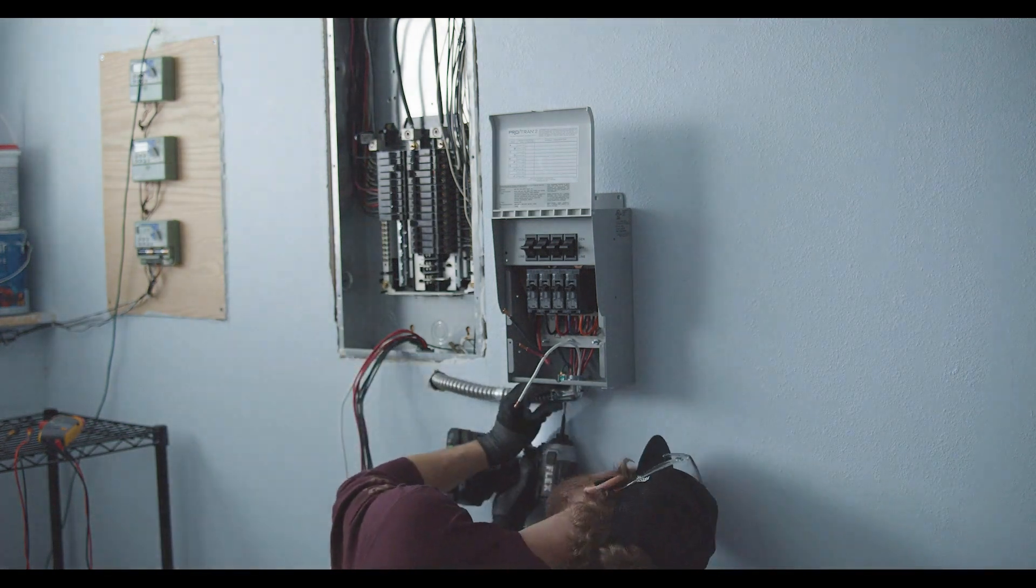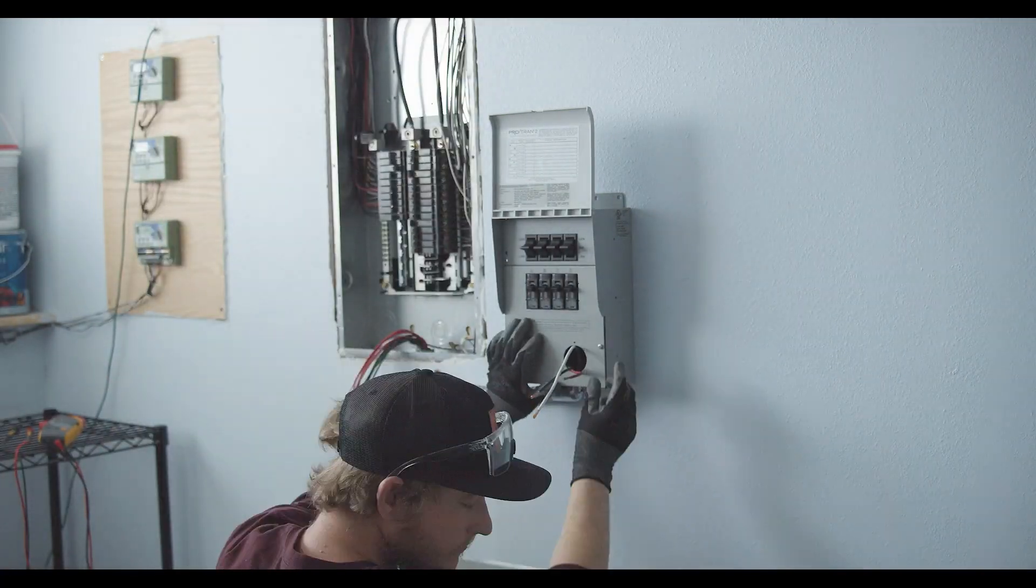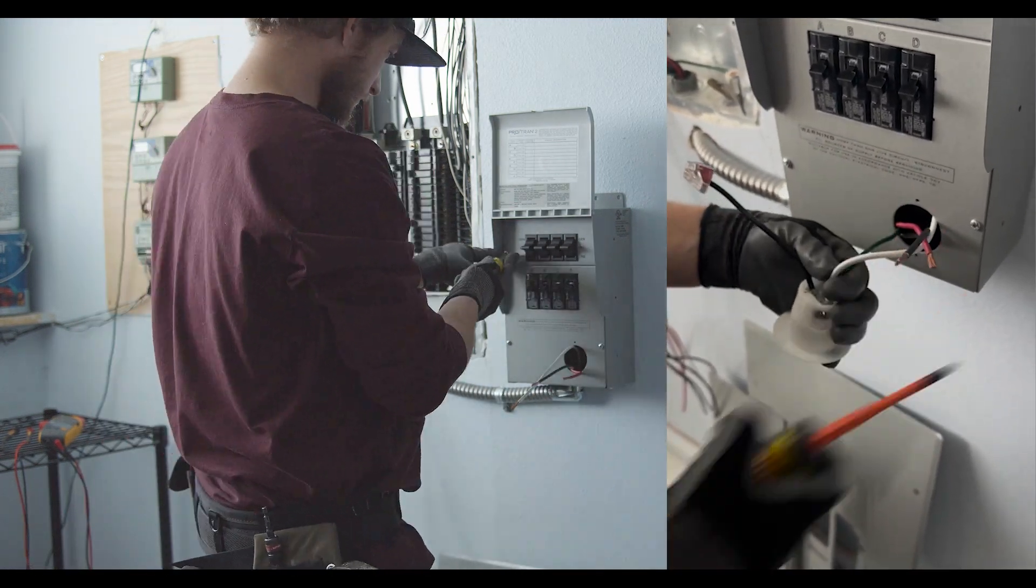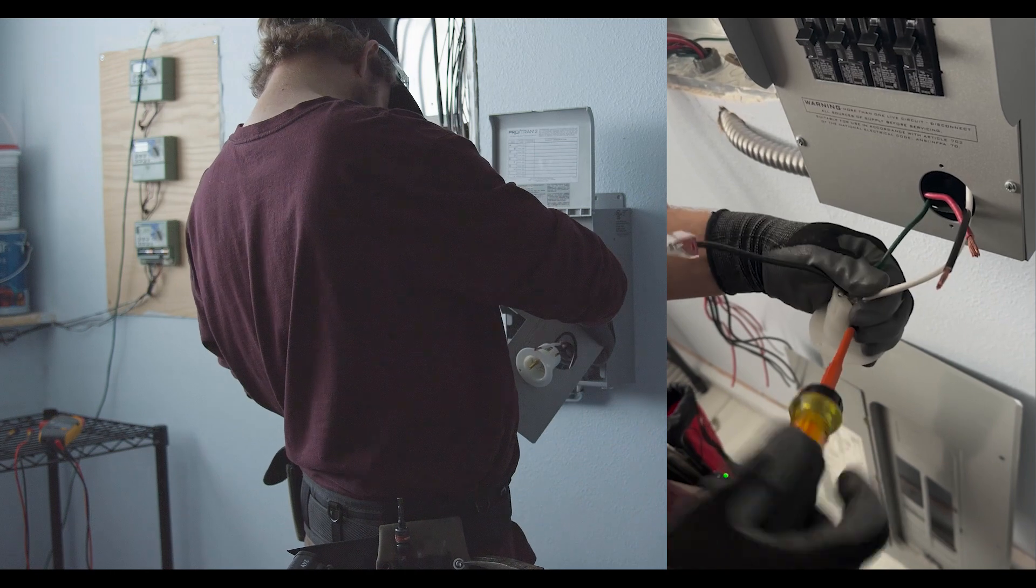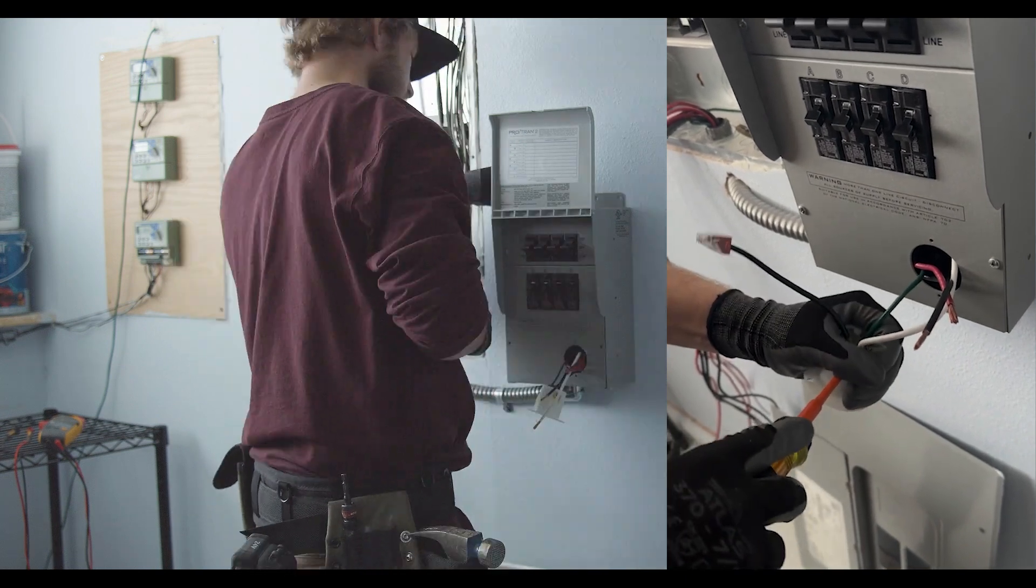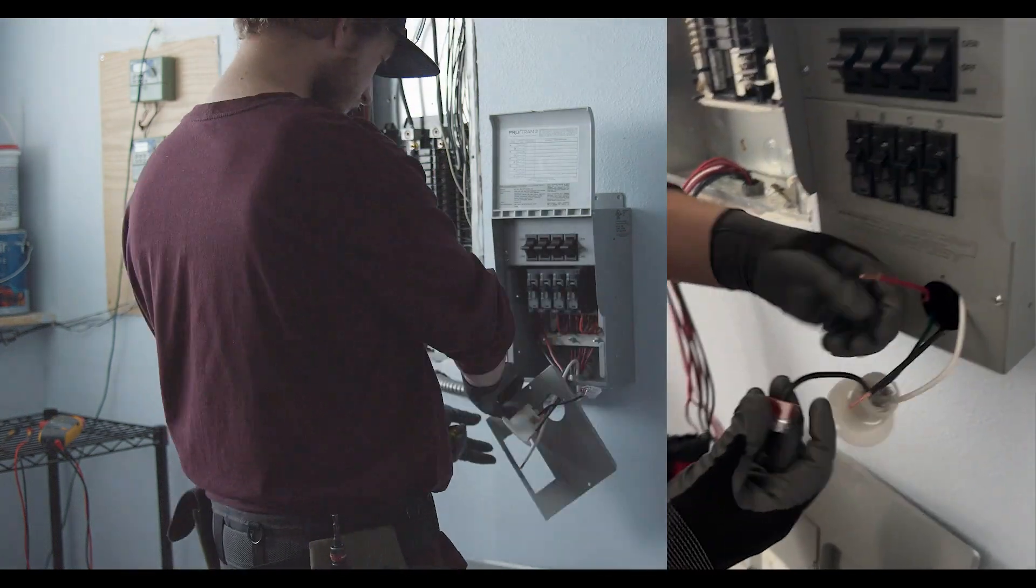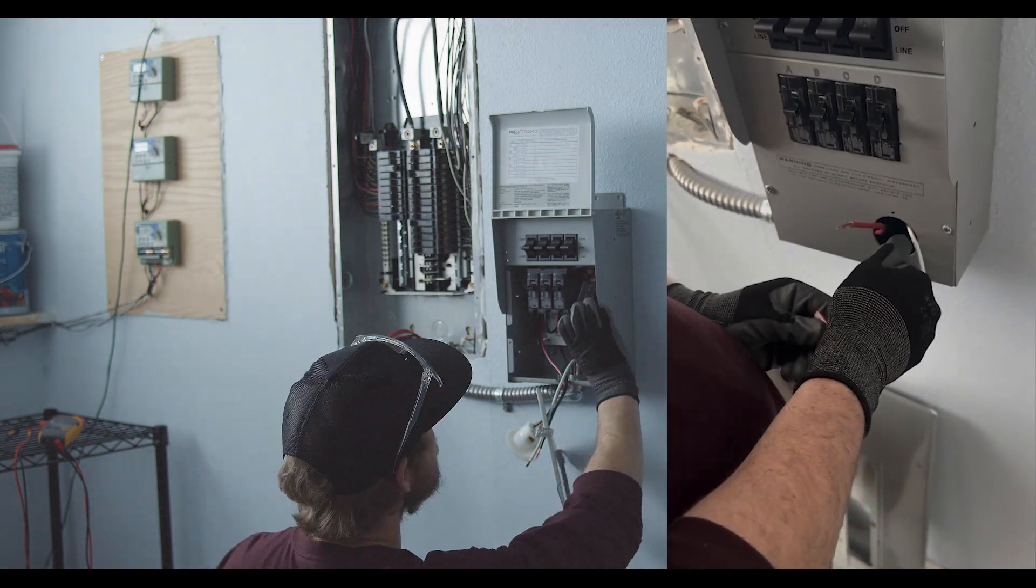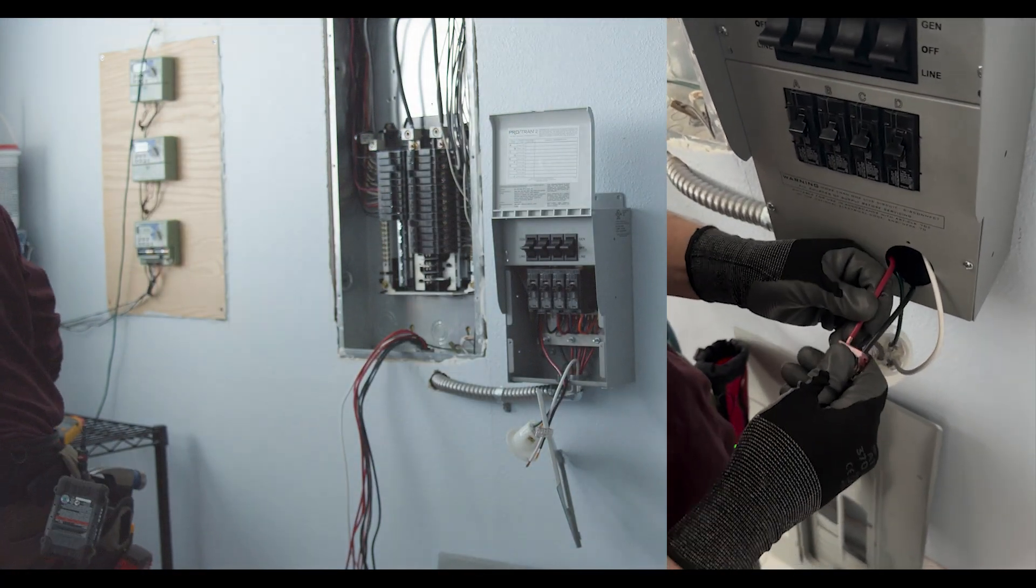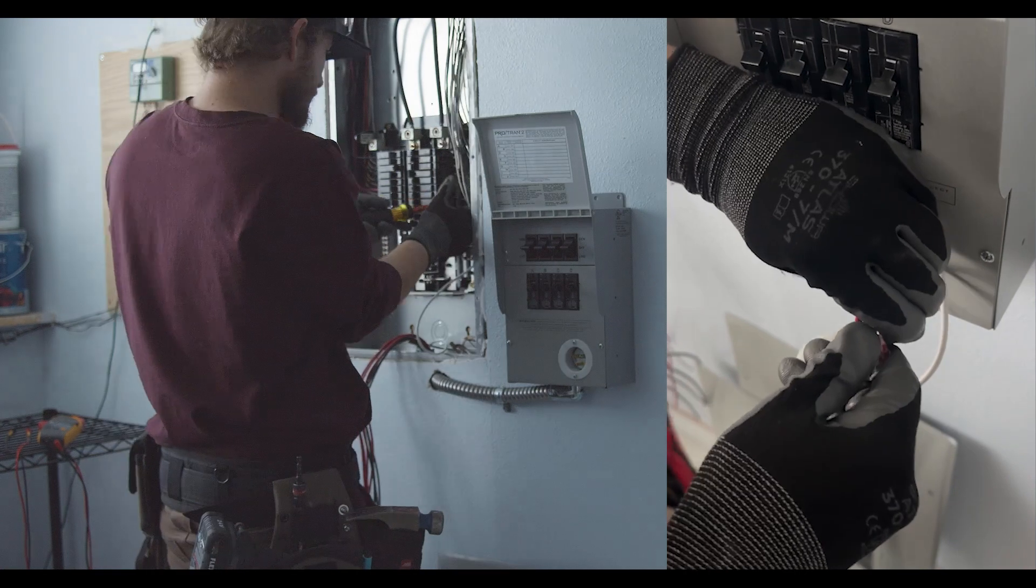So you will have a white wire that feeds through on the transfer switch. That's your neutral and that goes to the plug that will be installed on the cover of the transfer switch. With the plug you'll have a three port connector and you'll have a ground wire. The ground wire goes with the screw and the other ground wire on the cover of the transfer switch. The black and red wire will actually go into that three port connector and then the neutral goes on the silver screw on the connector. Once you have that tied in you can reinstall the cover and install the input connection.